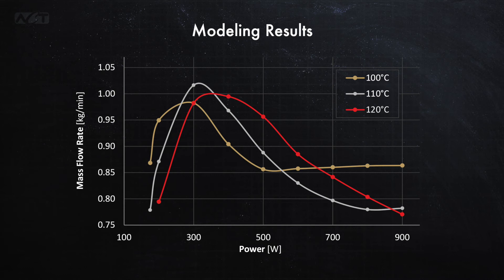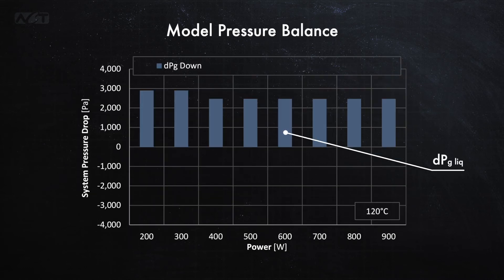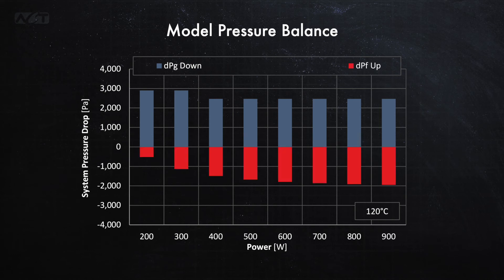So why do we see this increase in flow rate followed by a decrease at a higher power? The answer lies in changes in pressure drop around the loop. To illustrate this, let's look at the liquid gravitational head versus power for the 120 degrees Celsius case. Since the total system pressure must be balanced, we know that there must be negative pressure drops balancing out this liquid head. The first of these pressure drops is the frictional pressure drop in the two-phase flow between the evaporator and the condenser.